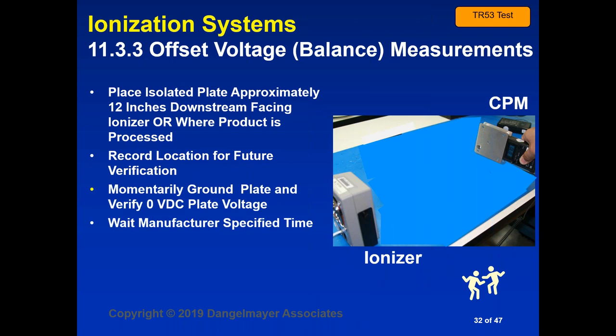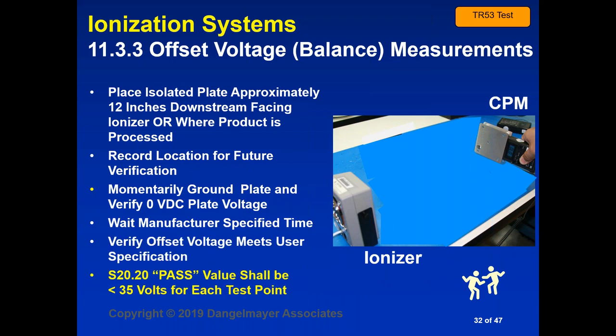You're going to momentarily ground the plate of the instrument and verify that it reads 0 volts. Then, holding it in front of the ionizer, as shown, you're going to wait a manufacturer-specified time. Depends on the ionizer, but typically it's 1 to 5 minutes. And then you're going to verify that the offset voltage meets the user specification. Now, S20.20 specifies that the pass value shall be less than 35 volts at each test point. And that's what you're going to be looking for in this measurement of your ionizer offset voltage, that it remains below 35 volts.